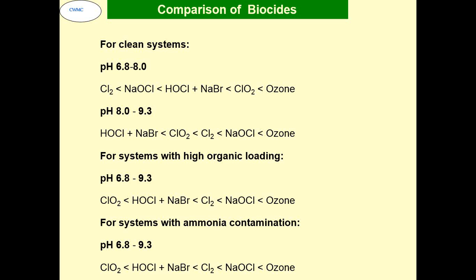Now, if we compare the different oxidizing biocides, for a clean system with a pH of 6.8 to 8, chlorine is the cheapest one, followed by sodium hypochlorite, and then the costliest is ozone. At pH 8 to 9.3, hypochlorite plus sodium bromide is supposed to be cheaper. Chlorine dioxide is a good choice there. Ozone again is the costliest one. For systems with high organic loading and pH 6.8 to 9.3, chlorine dioxide is the cheapest and the most effective biocide. Ozone is effective, but very costly. For systems with ammonia contamination and pH of 6.8 to 9.3, again chlorine dioxide is the cheapest and technically viable option.